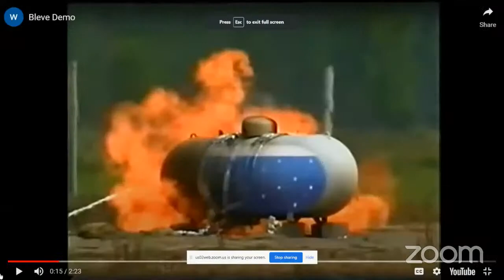When a tank is exposed to sustained heat, such as from a fire, the liquid in the tank is forced to boil or vaporize, resulting in increased pressure in the tank. To prevent overstressing the tank, the relief device activates, venting the excess pressure. As pressure decreases in the tank, the valve begins to close. With continued heating, pressure again builds, causing the relief valve to reopen.